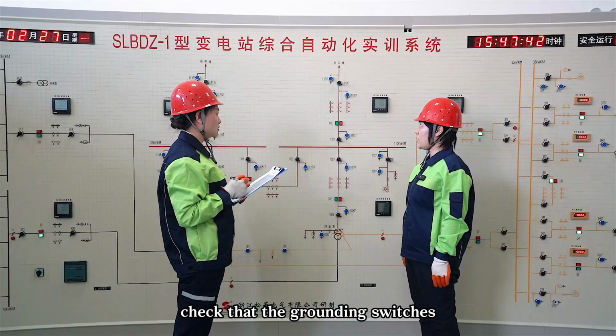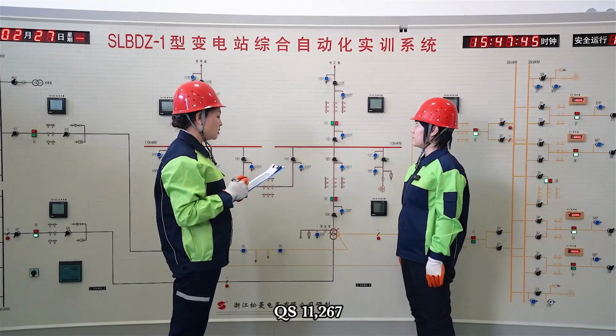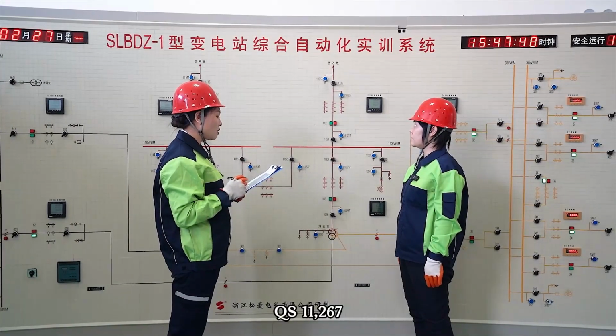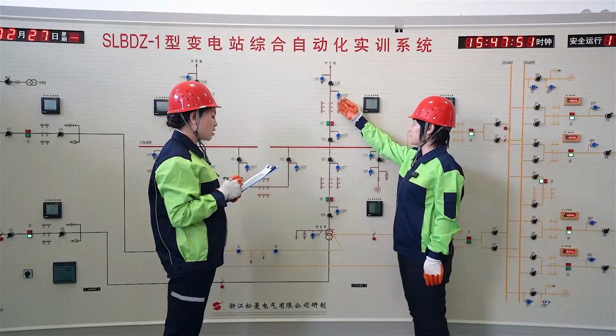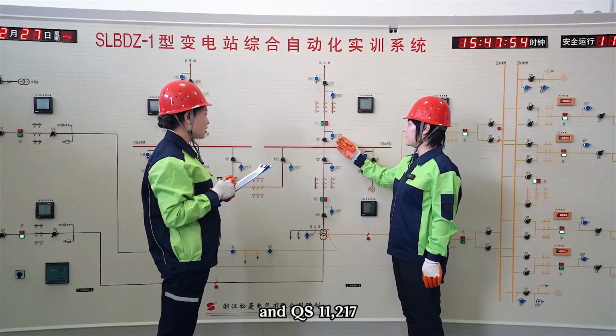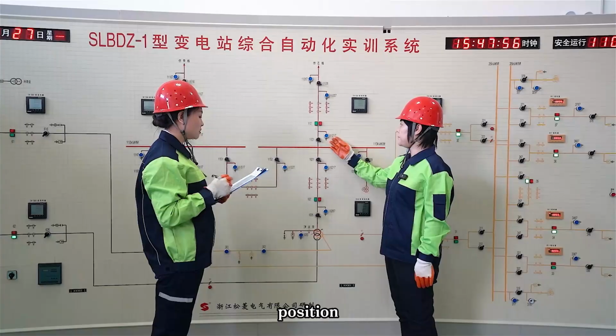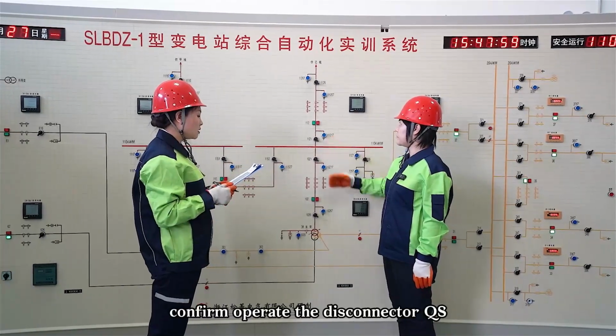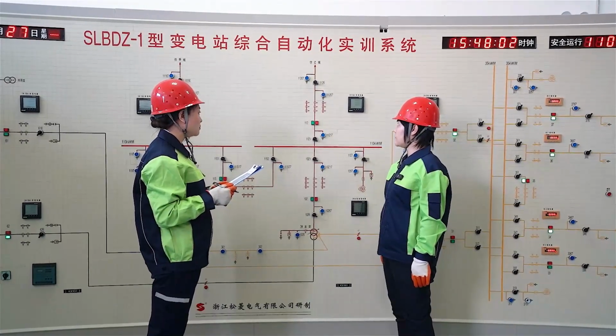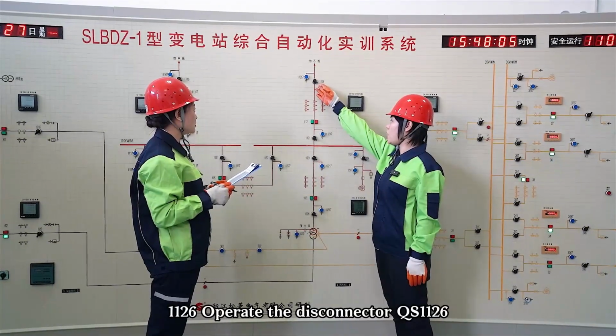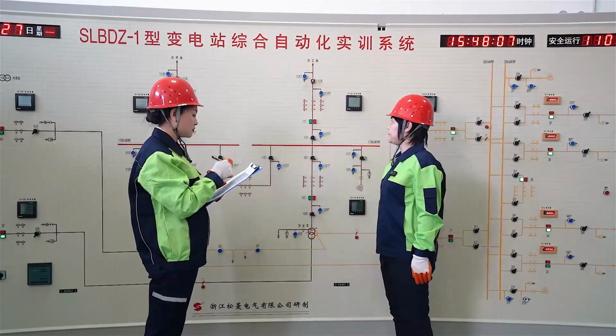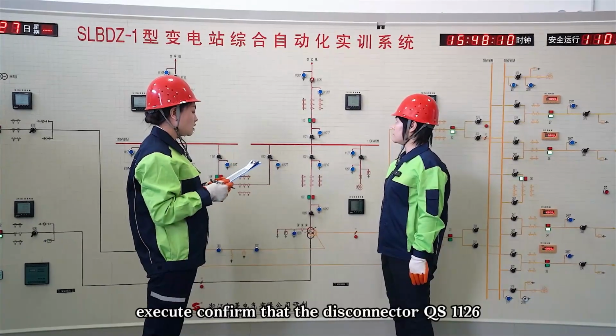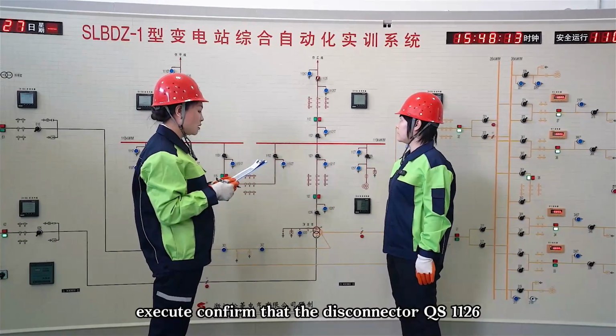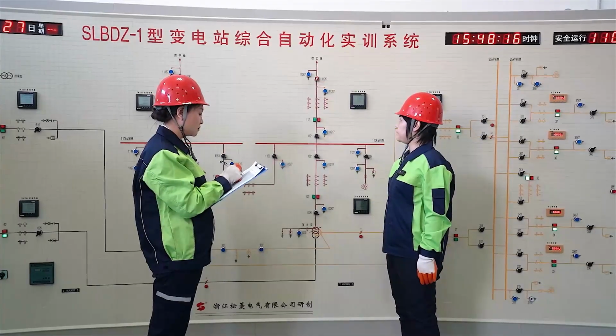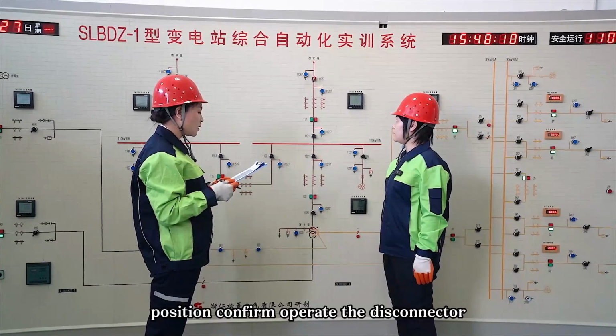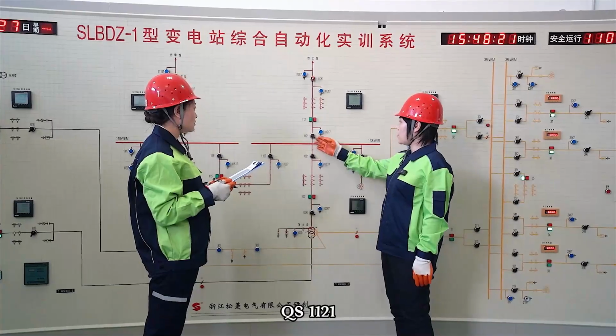Check that the grounding switches QES 11267, QES 11207, and QES 11217 are in the open position. Confirm. Operate the disconnector QES 1126. Operate the disconnector QES 1126. Execute. Confirm that the disconnector QES 1126 is in the closed position. Confirm. Operate the disconnector QES 1121.